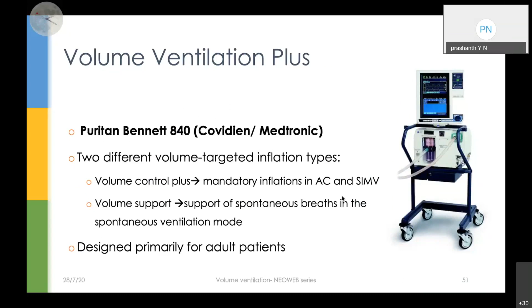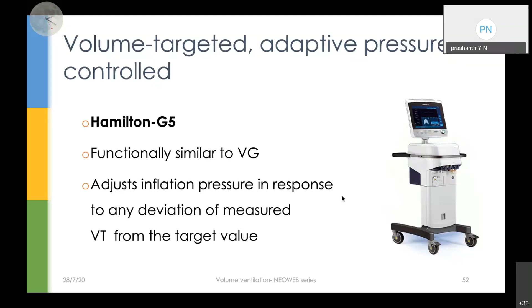And Hamilton G5 also has volume targeted adaptive pressure control, which resembles our volume guarantee. It's functionally similar to it, but this also has basically been looked at in adult patients rather than in newborns. So until now, the evidence and what people have been using and what has been published is more so with Babylog 8000, and now probably VN500 has taken over from Draeger. And the other thing which they've started using is the SLE ventilator. More and more evidence is for these two ventilators rather than the other ventilators which I just mentioned.